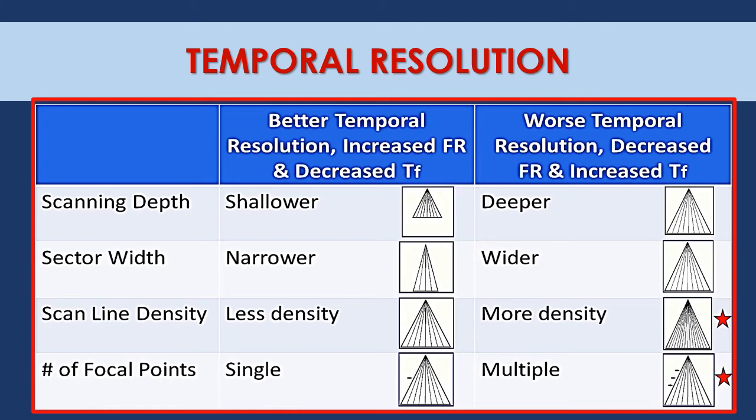How many scan lines here? I will get the time of the frame will get longer, right? So deeper scanning, I will get longer time of the frame, I will get lower frame rate, and I will get worse temporal resolution.